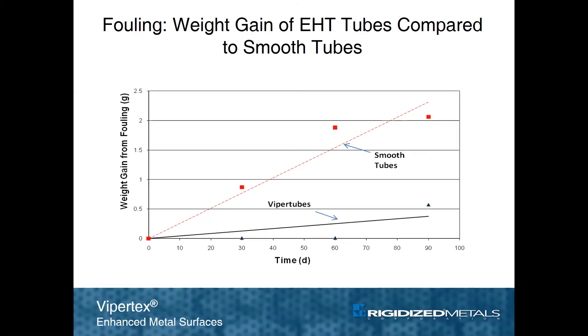Tests indicate a significant delay in the onset of fouling in a Vipertex tube compared to smooth. This is due to turbulent flow and the shear condition created by pattern features that make it more difficult for contaminants to accumulate on the enhanced tube's surface.